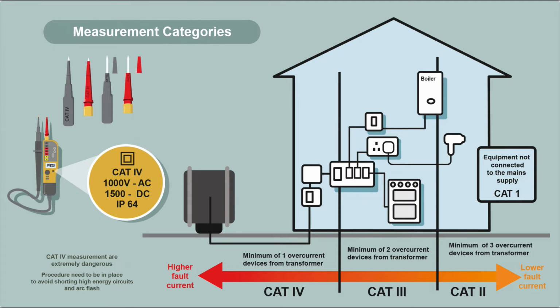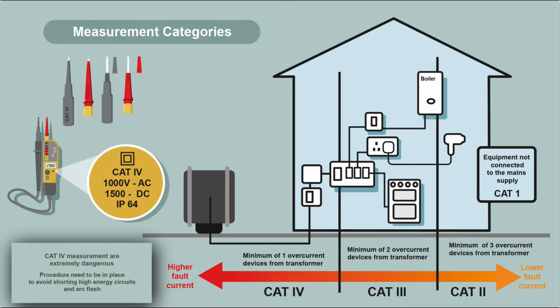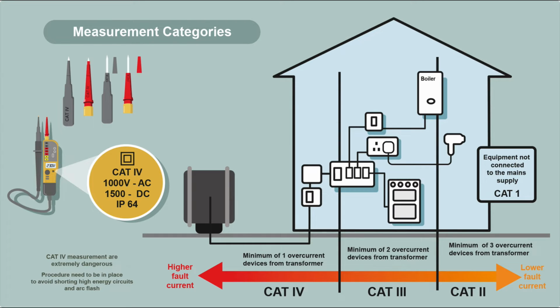It'll be stamped on the actual probes. With the cover on, it's category 4. With the cover off, it's category 3. The reason being, it's more dangerous. Category 4 measurements, that's very dangerous. You need procedures in place to avoid shorting high energy circuits and creating arc flash. The categories blur into each other because you think in your fuse board, I've got 2 protected devices from the transformer, so that's category 3. If you think your main switch in the consumer unit, there's only 1 protected device between you and that transformer, so you would need a category 4 voltage tester. In category 1, that is for equipment that's not normally connected to the main supply.